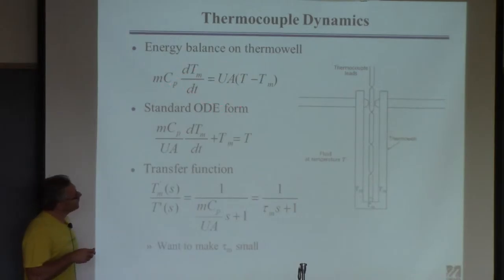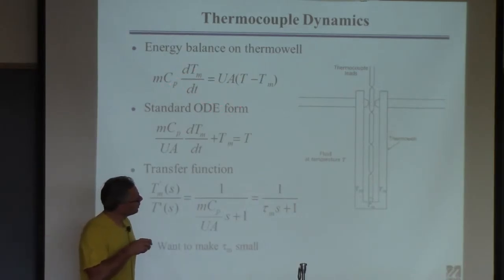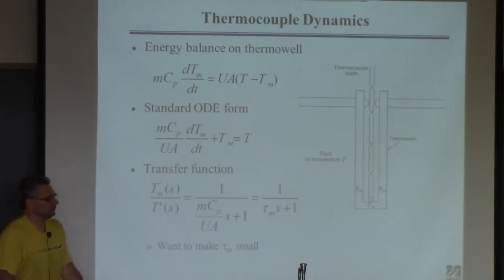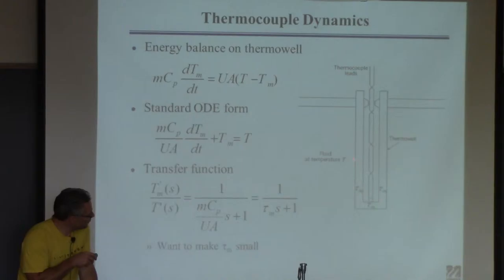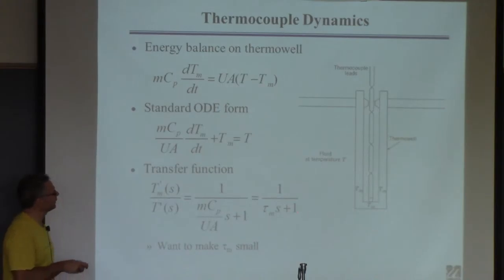So here's the way a real thermocouple works. Here's the fluid, probably flowing in most cases, though it might be stagnant. You have a thermocouple well. The thermocouple sits inside this thing because you don't want to put the thermocouple in the fluid itself. So what has to happen to sense temperature? You have to have heat transfer through this wall to the thermocouple. Obviously you don't want to make this thermal well out of an insulating material.